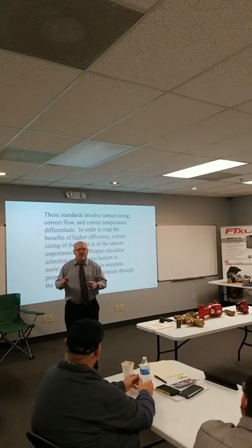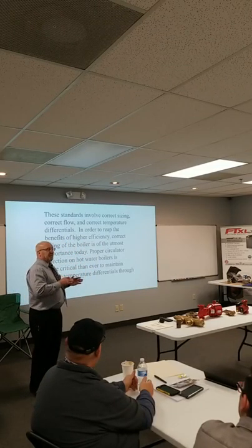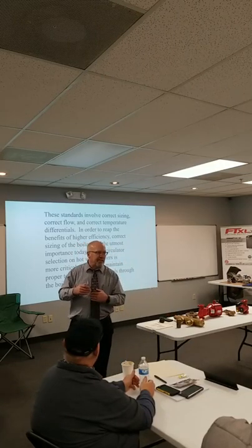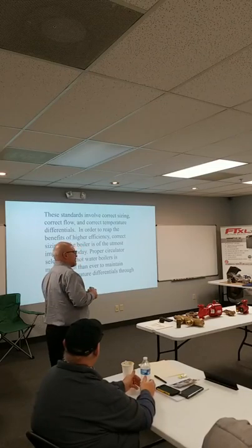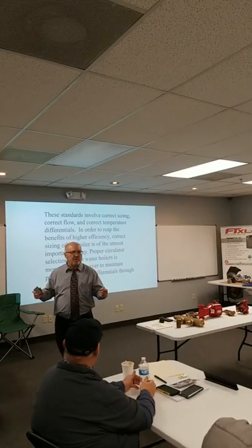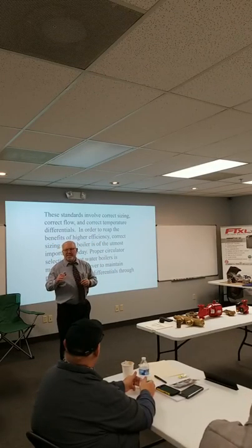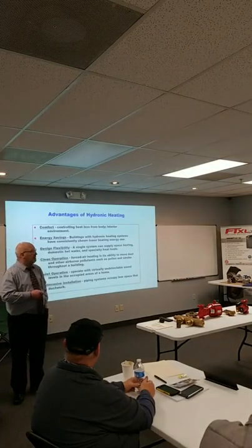Yeah. Never size pipe based on the connection to the equipment. Size it based on the flow you want to get there. Because the manufacturer makes a certain connection at his piece of equipment to get the heat transfer or the velocity through his heat exchanger or his pump or something like that. I have commercial pumps that have a 3-inch suction and a 1.5-inch discharge on a 3-inch pipe system. It has nothing to do with what pipe size you're using. It's just the characteristics of that pump. So never pipe based on connection size. Always base it on flow. So you need to understand what that flow is and where it belongs.